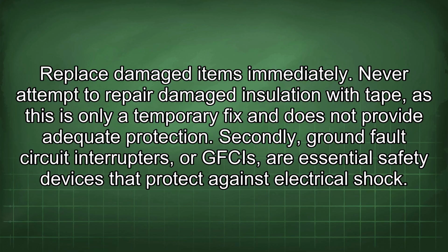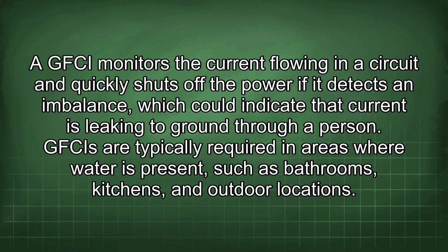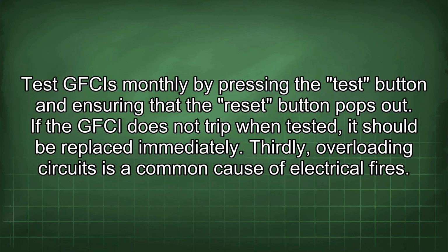Secondly, ground fault circuit interrupters, or GFCIs, are essential safety devices that protect against electrical shock. A GFCI monitors the current flowing in a circuit and quickly shuts off the power if it detects an imbalance, which could indicate that current is leaking to ground through a person. GFCIs are typically required in areas where water is present, such as bathrooms, kitchens, and outdoor locations. Test GFCIs monthly by pressing the test button and ensuring that the reset button pops out. If the GFCI does not trip when tested, it should be replaced immediately.